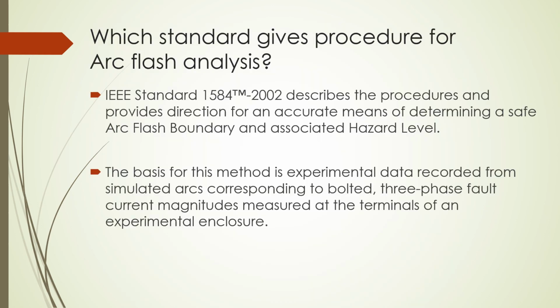Which standard gives procedure for arc flash analysis? IEEE standard 1584-2002 describes the procedure and provides the direction for accurate means of determining a safe arc flash boundary and associated hazard level. The basis for this method is experimental data recorded from the simulated arc corresponding to bolted three-phase fault. Current magnitudes were measured at the terminals of an experimental enclosure.